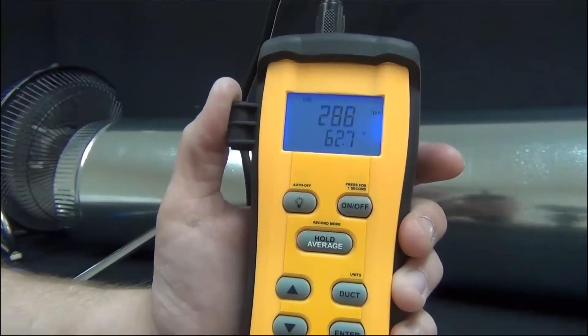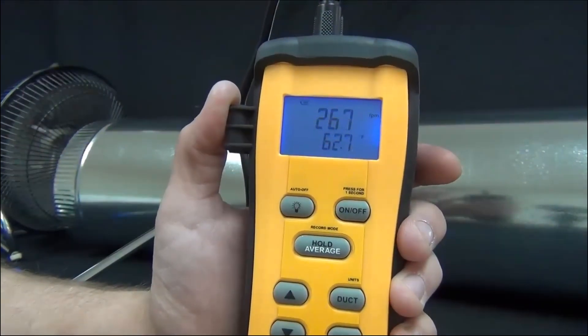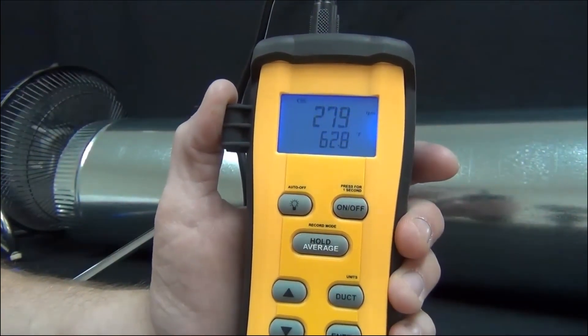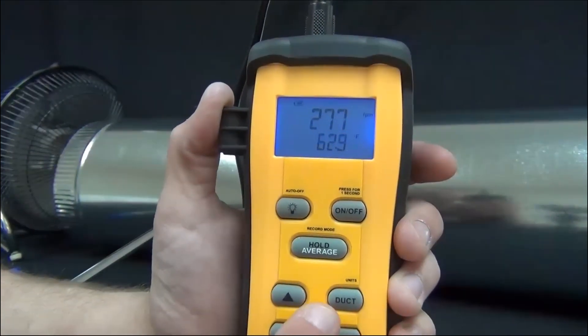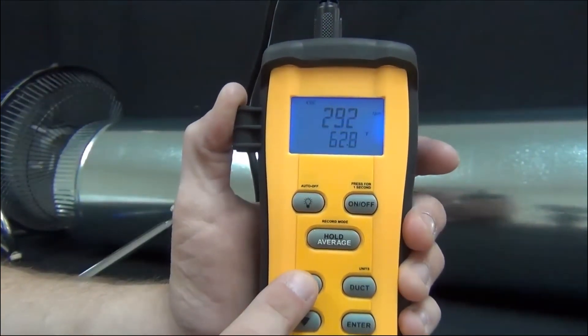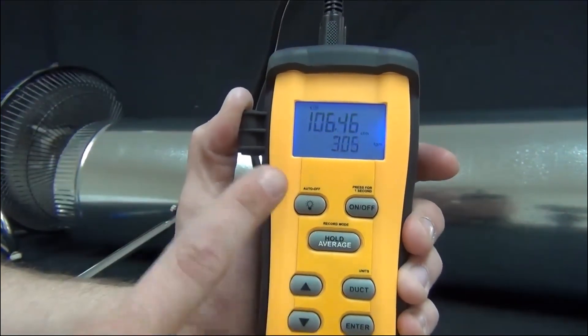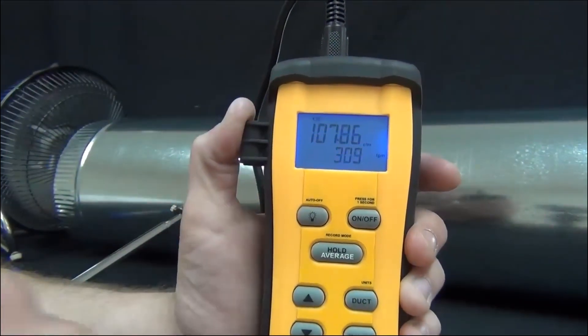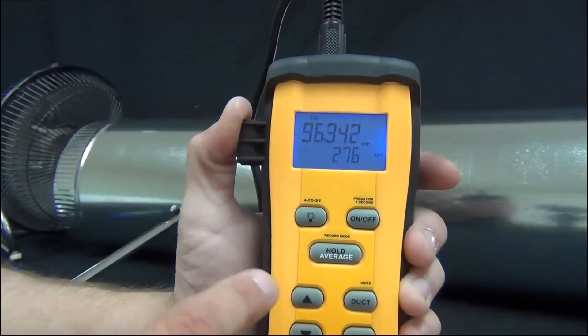Now it's back on the feet per minute. So the hot wire anemometer is reading about 270, 280 in there somewhere for the feet per minute. To change modes, while you're reading the feet per minute, just press the up arrow. And now I'm reading 108 CFM based on the eight inch diameter duct that I entered in.